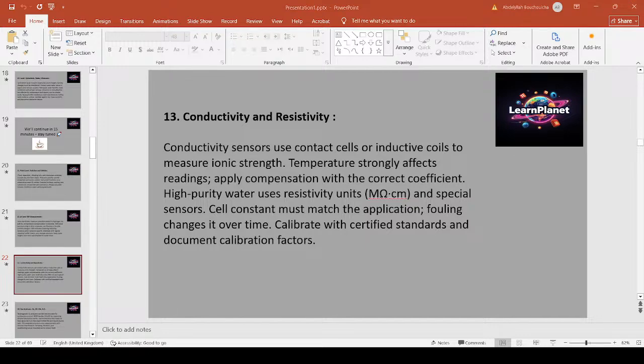Conductivity sensors, conductive or inductive, measure ionic strength. Temperature compensation with an alpha coefficient is mandatory. For ultra pure water, use resistivity measurements in megaohm-centimeters and special cells to avoid contamination. Fouling alters the effective cell constant, so schedule cleaning and recalibration. Always calibrate with certified conductivity standards and track cell constants. Example: in boiler feed water control, use a temperature compensated conductivity transmitter with routine calibration to avoid carryover and scaling.